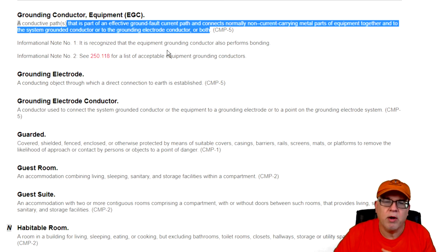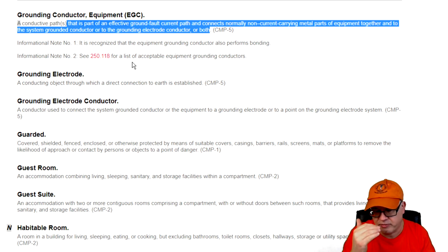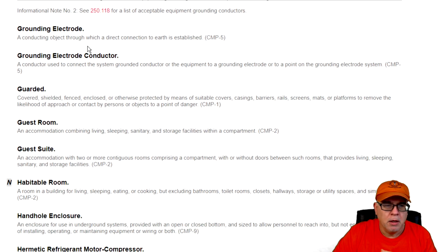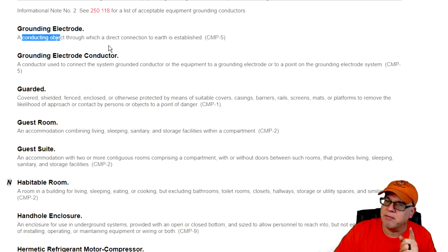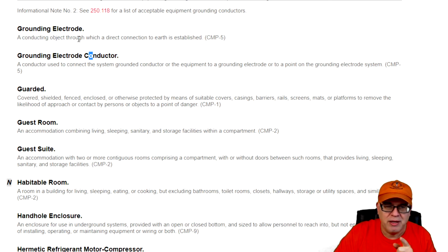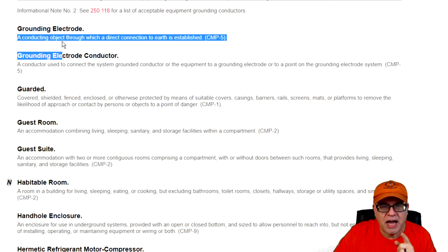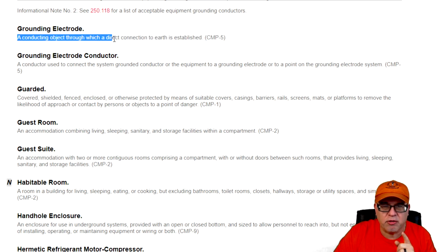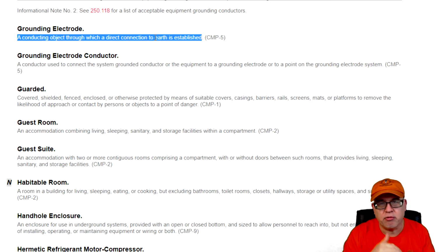And here, we also give you a list at 250.118 to let you know what is considered an acceptable equipment grounding conductor. And it's a long list, okay? Grounding electrodes, what are those? Okay, it's a conductive object. It used to say device, but that was the wrong terminology to use. It is a conductive object through which a direct connection to earth is established. Ground rods, it's directly driven into the earth. Okay, that is a grounding electrode.